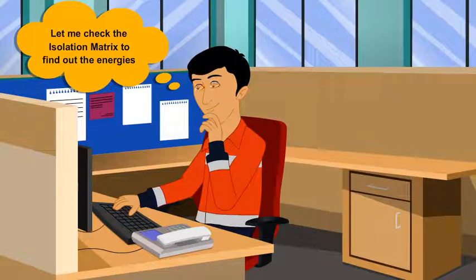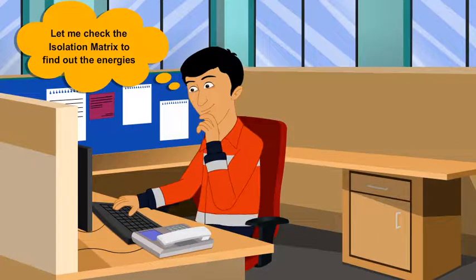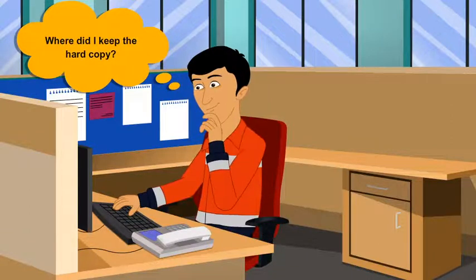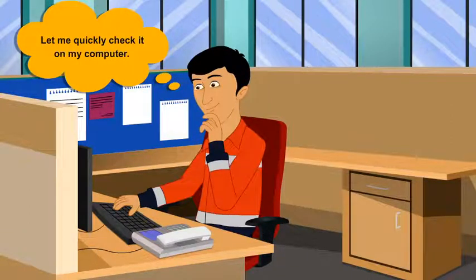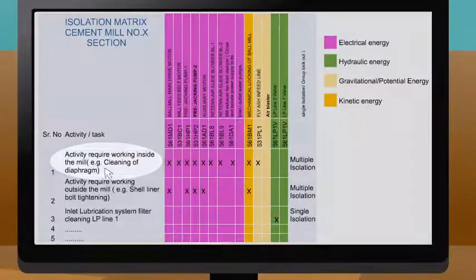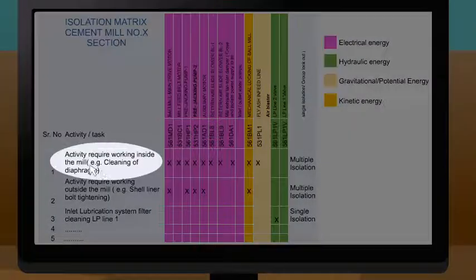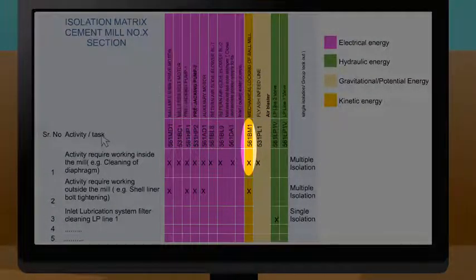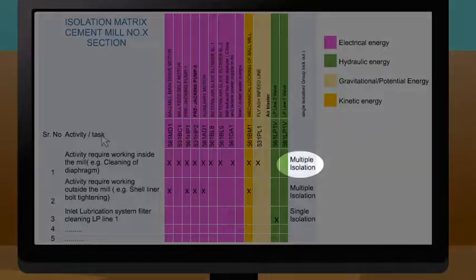Dev checks the isolation matrix — first looking for a hard copy, then checking it on his computer. For this activity, he identifies the electrical energies and a gravitational energy that must be isolated. He notes this will be a multiple isolation process.